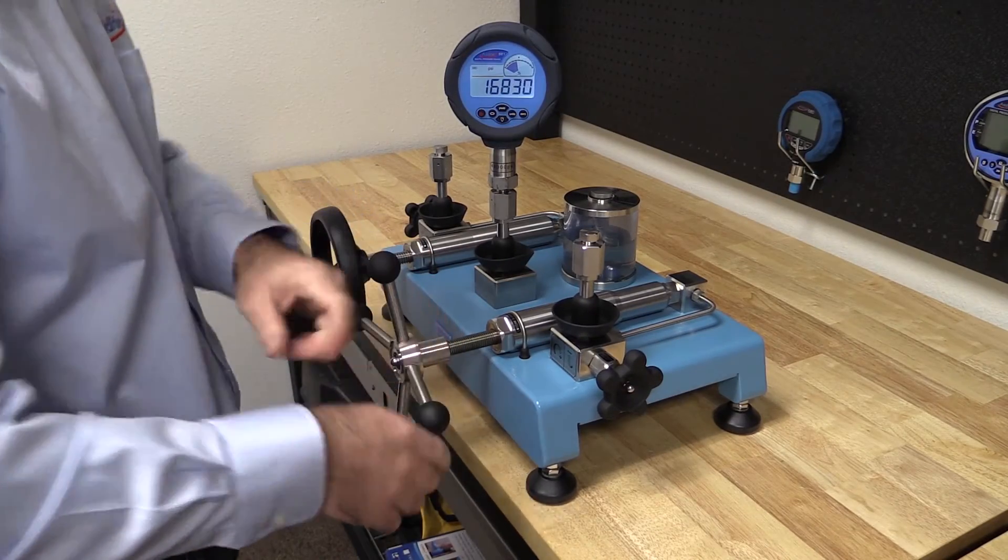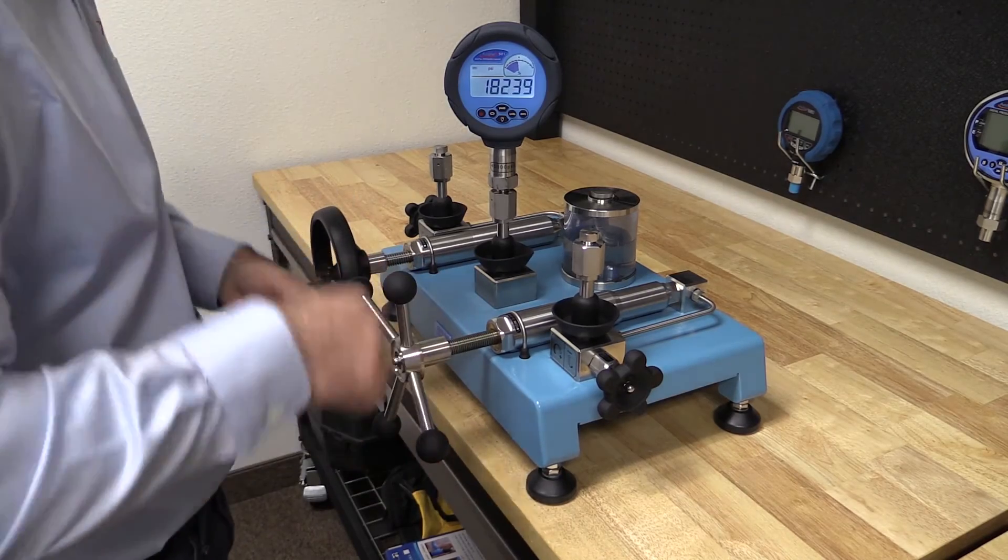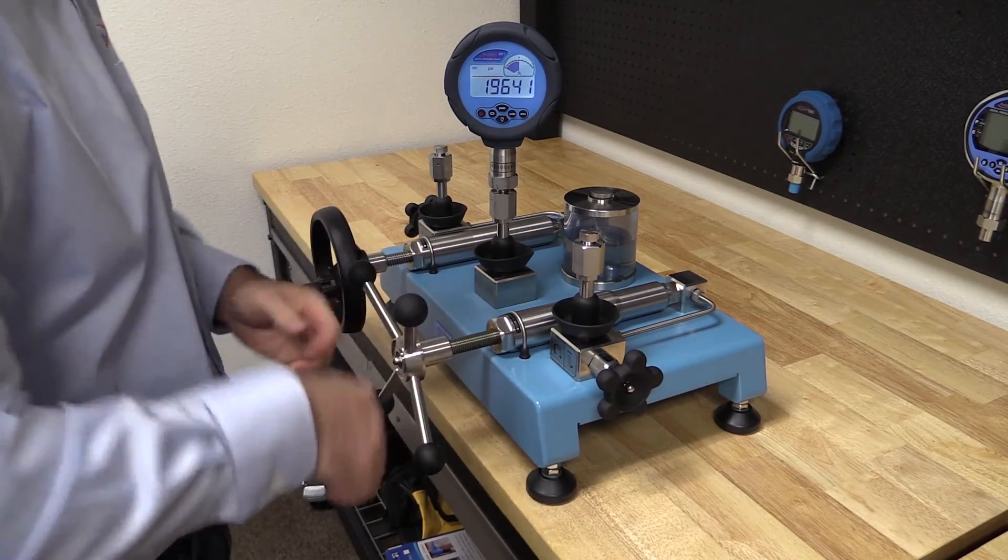Once you see a good vacuum being pulled and very few bubbles emerging in the liquid reservoir, then we are ready to start generating pressure.